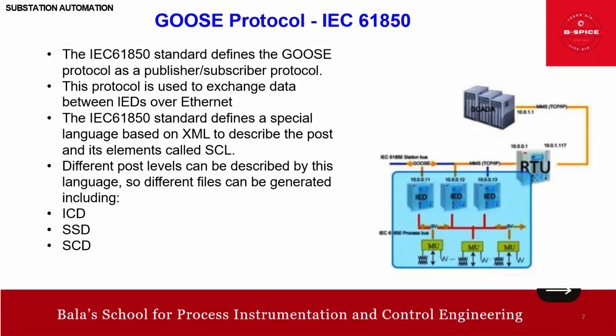Okay. So another point in GOOSE is VLAN and priority tagging. GOOSE uses VLAN, meaning virtual local area network, and priority tagging as per the IEEE 802.1Q standard. This allows the creation of a virtual network within the same physical network and sets a priority level for messages, ensuring that critical data is transmitted with high priority. So that is the beauty. So VLAN and priority tagging.